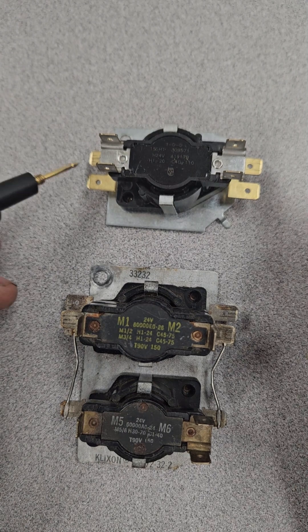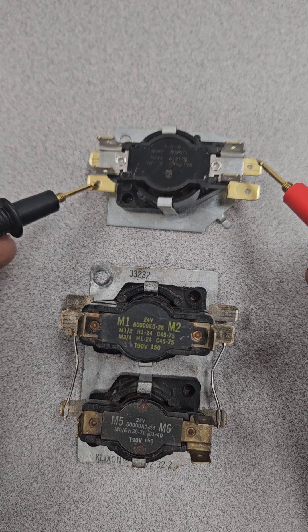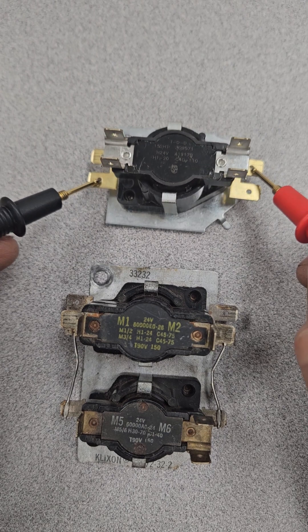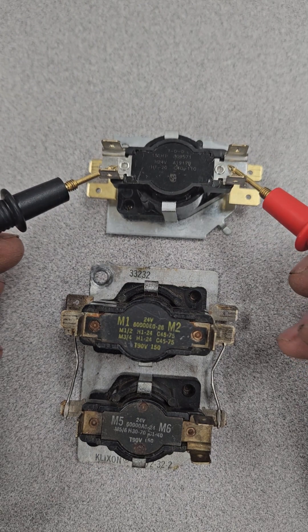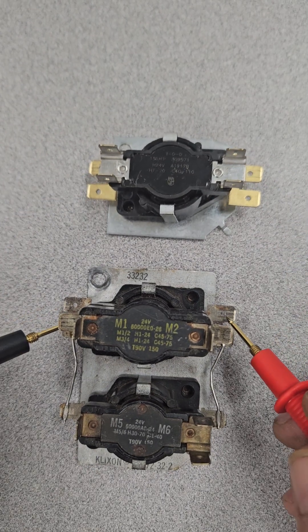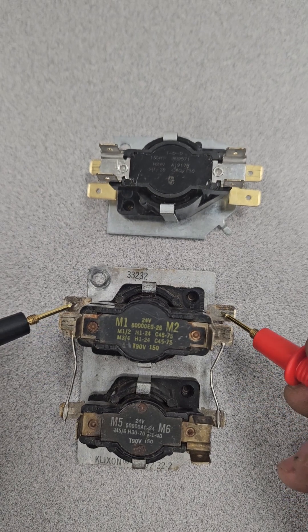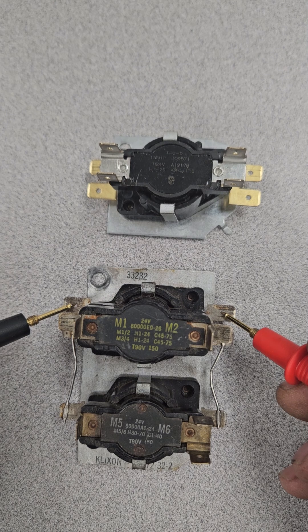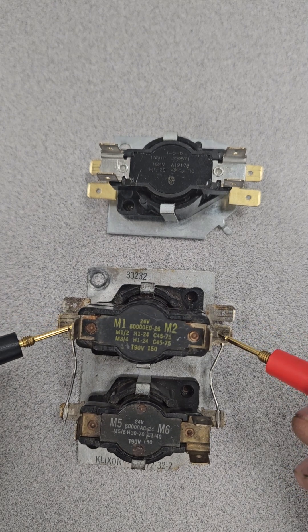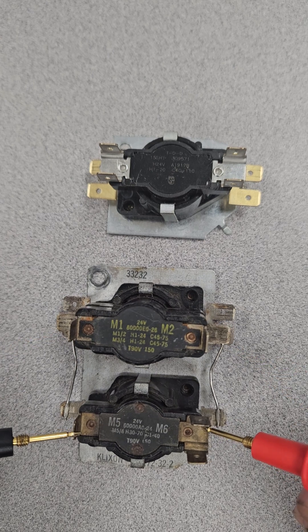Electrically, we'll check these to make sure that they are good. We're going to test first. Got continuity between our leads. I'm getting 0.092 ohms on that one, and it should be a closed switch, and it is there. I would actually have to cut the wire between these to check to see which ones are good or not good, but we can see that electrically it will pass electricity through the coil or the heater and that the switches are in the correct position.